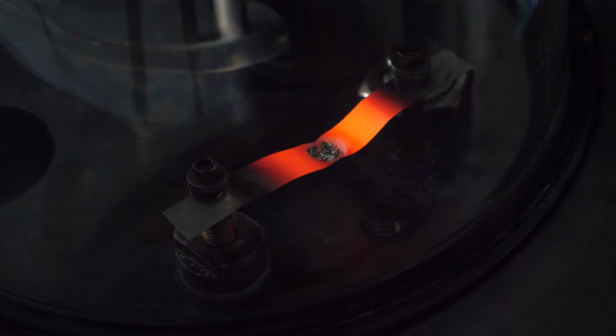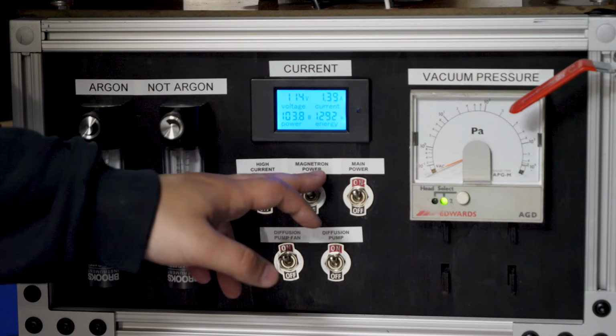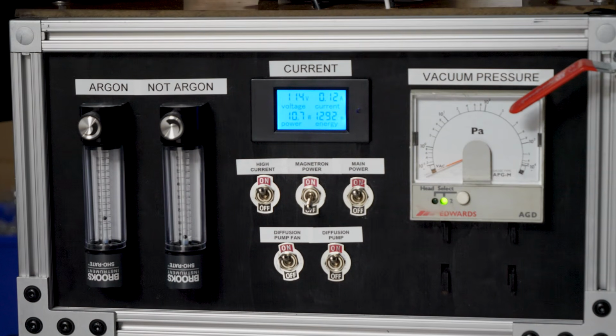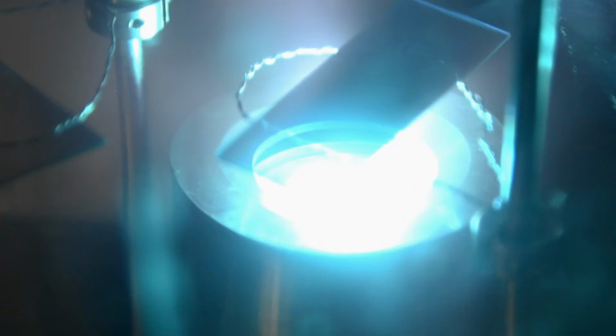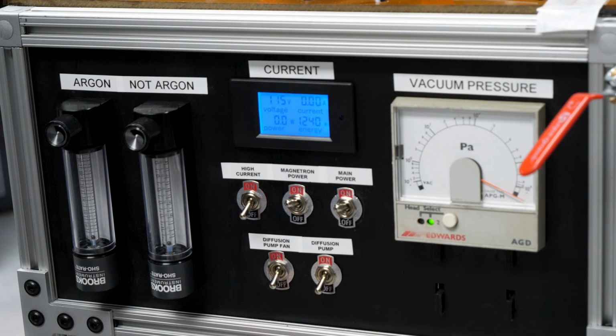This way, I can throttle the amount of power going into either system. I can also control which one is on from the control panel thanks to a few switches. What's great is that there's a lot of redundancy. To actually send any power into the system, you need to flip 4 switches in a variety of places, so you really need to be sure that you want to do it.